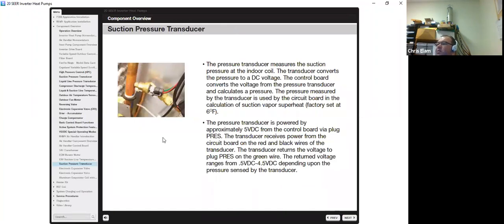You have your suction pressure transducer. The transducer measures the suction pressure at the indoor coil. You also have them on the outside unit as well. The transducer converts pressure to a readable DC voltage. The control board converts the voltage from the pressure transducer and then calculates a pressure. If you have the EcoNet hooked up, at any time you can actually view the pressure of the indoor and the outdoor based on the transducer readings.